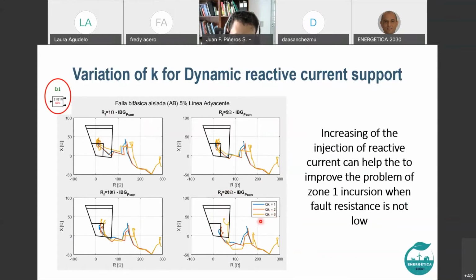This is important, but of course you have to keep in mind that if you increase the reactive current support, you will decrease the active power the inverter is able to produce. If it's not important for your system that the active power is reduced during the fault, okay, you can do it. But if your voltage stability, for example, depends on not removing so much active power, in the case of weak grids like we have now, then we have to find a good balance. We have to take care about that.